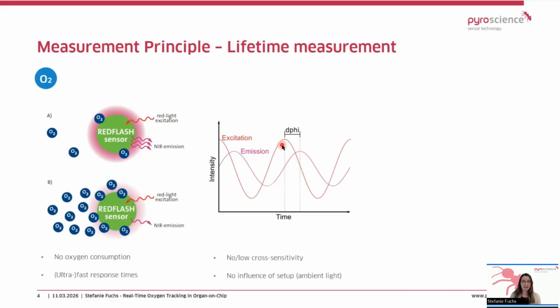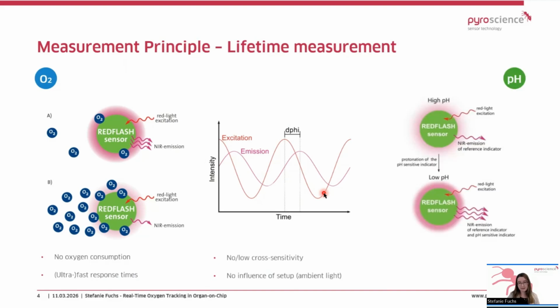From this, we can calculate all the way back to all different oxygen units, which you will also get in the measurement. And by using this technique, we are not interfered by any blockage of the light path, which might occur to the cells, for example, or small inhomogeneities of the illumination. So it is a really robust readout. And our other sensors, pH, work very similarly, so that everything is compatible to each other.